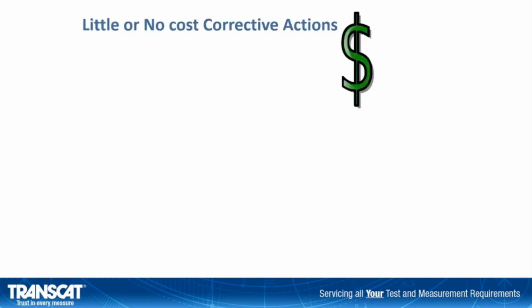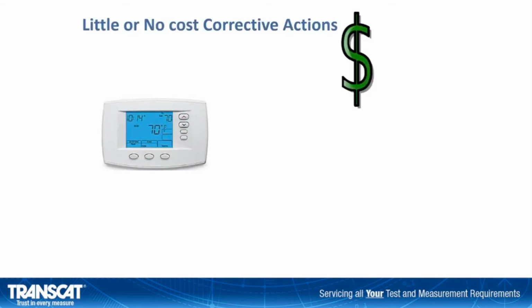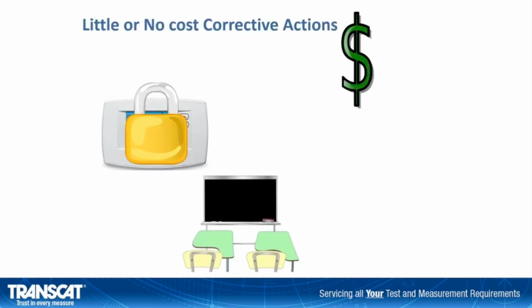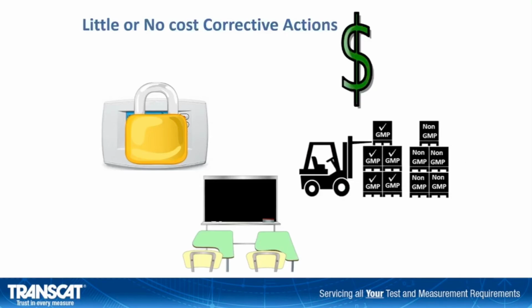Some little to no cost corrective actions include optimizing the programming of your HVAC system, installing a password or a lockbox over thermostats to ensure that your settings are not tampered with, training your staff in the importance of limiting outside air from entering the building through better policing of the door and limiting loading and unloading times, marking failing areas for non-GMP storage to be used for items that are not temperature sensitive.